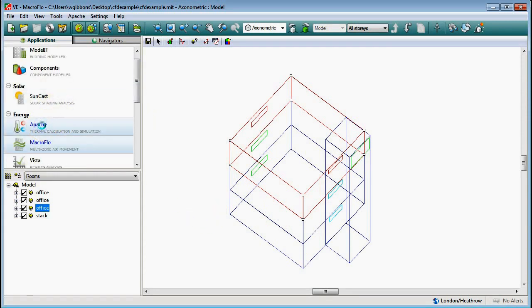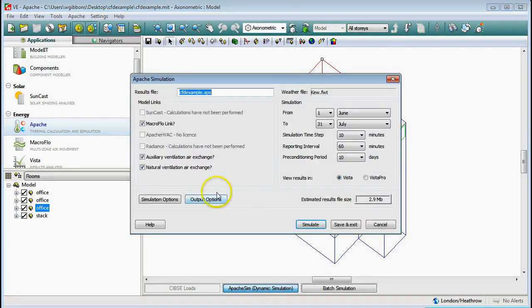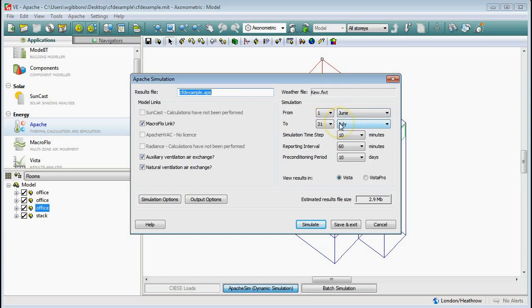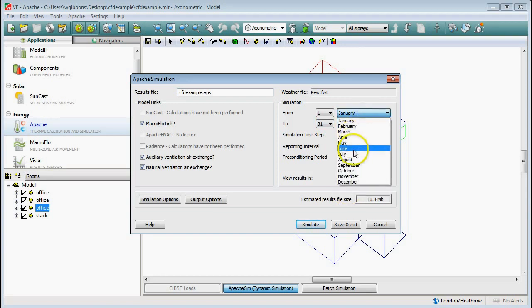So I need to run this model now. I'm going to go into Apache and come down to Apache Sim. Now there are a couple of things to watch out for at this next stage. First, make sure that the macro flow link is ticked - we need that otherwise those windows are not going to be simulated. I've reduced the time frame to just June and July just to speed things up a little bit.